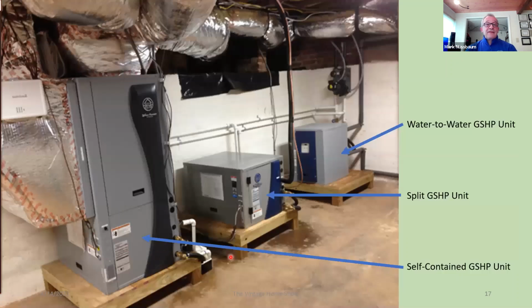So there are places where that's really the only way you can go, which is why we use them. But if you have a choice, this isn't the most efficient method. Here's an example of a house that's got 3 different systems. It's got a self-contained system, probably serving the basement and first floor. It's got a split system that is probably connected to an air handling unit, maybe in the attic, to service the second floor. Then I've got a water-to-water unit that's producing hot water, maybe for domestic or for floor heat.